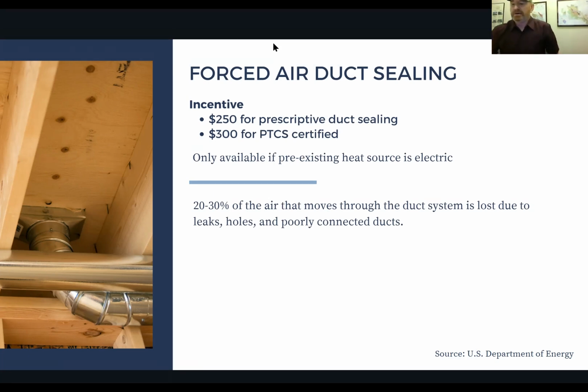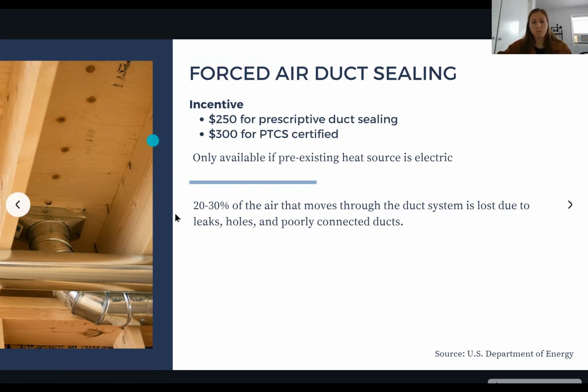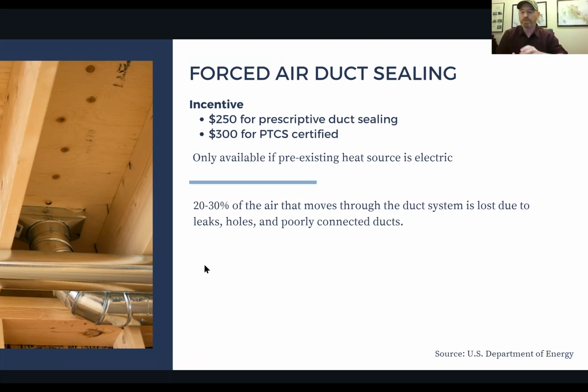How you can tell, some quick checks of if your ducting leaks. First of all, ducting will leak, even brand new stuff, but at a smaller rate. But kind of an easy check is if you go to the register, most registers are on the floor. It makes it easy in this case. If you lift up the grate on the register, you'll see the ring around where the boot meets the subfloor. That should be completely sealed around there. And the other thing is when you lift that, if the unit is not on, you should not have any smell of the attic or the floor or any type of rodent or something. There should be no smell. It should smell just like the rest of the house. So next slide.